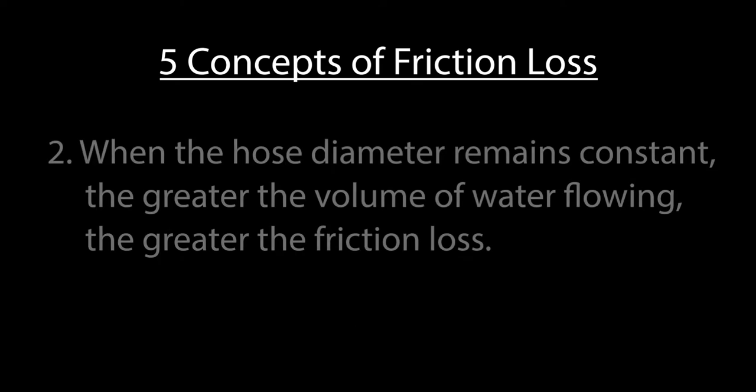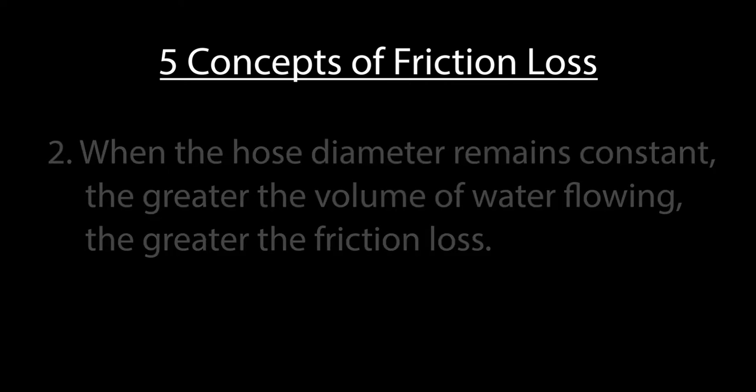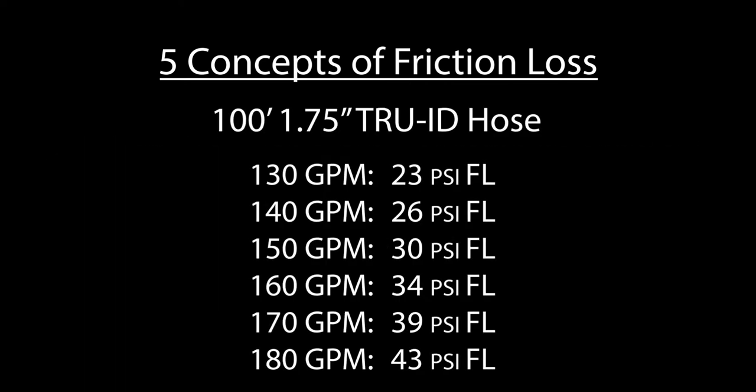Second, when the hose diameter remains constant, the greater the volume of water moving through the hose, the greater the friction loss. As you force more water through the hose, more turbulence is created.